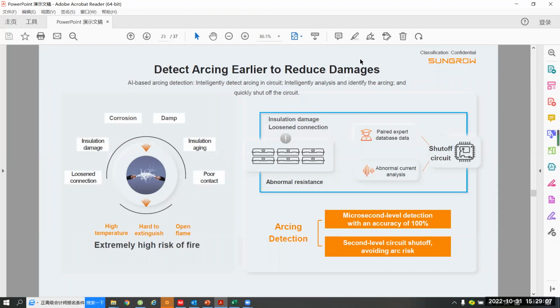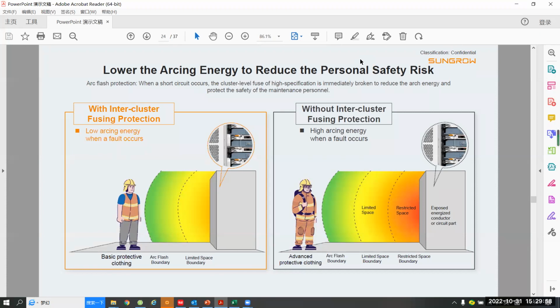And another important electrical safety design is the arcing protection. We also use AI technology to do the arcing detection and monitoring, such as loosened connections, insulation damage, corrosion, damp, insulation aging, and poor contact. Through all of this data monitoring, it can analyze and identify the arcing phenomenon intelligently, and then shut down the circuit at the second level to avoid the risk of arcing. So the arcing protection can detect the arcing earlier to reduce the damage of the ESS system. So all of this electrical safety protection can lower the arcing energy and electrical energy to reduce the personal safety risk.